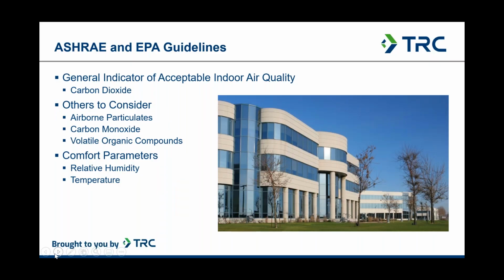So ASHRAE and the EPA provide guidance for certain parameters for acceptable indoor air quality. We've highlighted a few here for you today, and I'll explain how these might relate to COVID. So the first, carbon dioxide, is a byproduct of respiration. And if there's a buildup of carbon dioxide, it suggests that there may be insufficient outdoor air introduction or poor distribution or mixing of air in the occupied space, which is a very important consideration for COVID, as Leo had explained. Elevated levels of CO2 can cause lethargy, tiredness, or that feeling of stuffy air at the end of the workday.